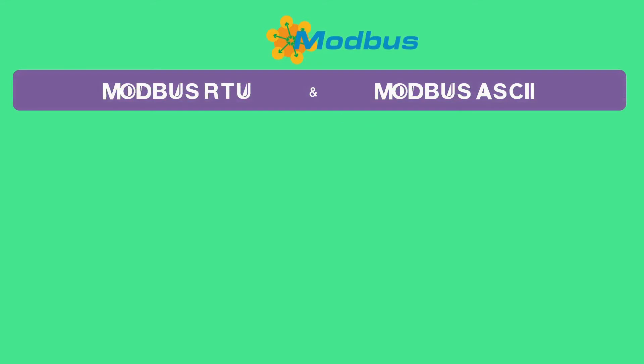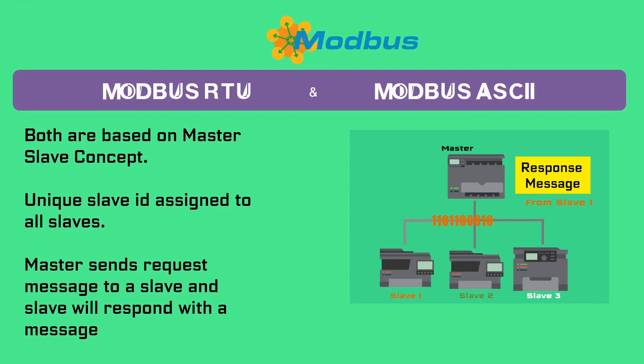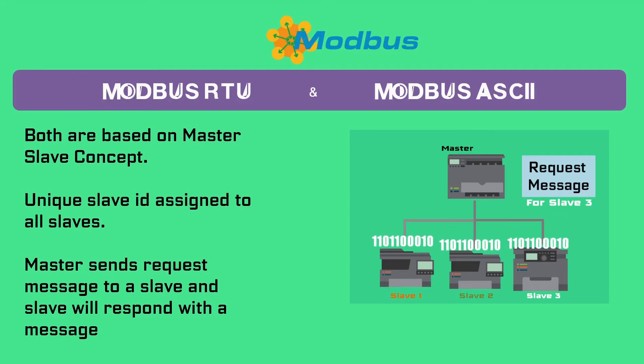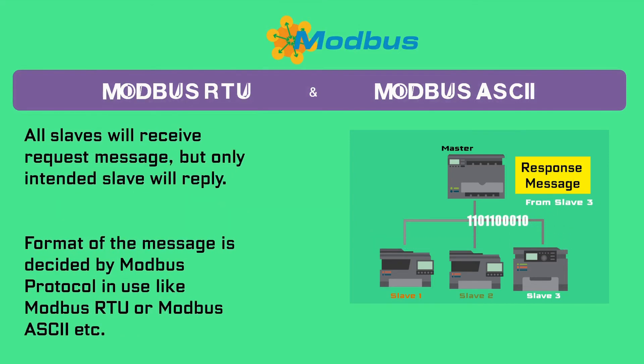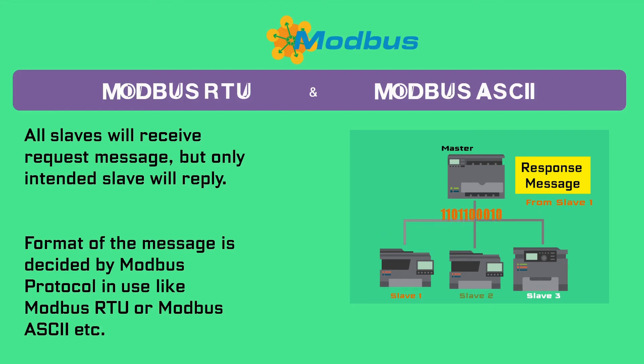In this session, we will concentrate on Modbus RTU (Remote Terminal Unit) and Modbus ASCII only. Both are based on the master-slave concept. In both, a unique slave ID is assigned to all connected devices except the master. The master sends a message to the desired slave with its slave ID, to which that slave node responds. All other slaves also receive the message, but only the slave whose ID matches the received message will respond. The format of the message is decided by the Modbus protocol.